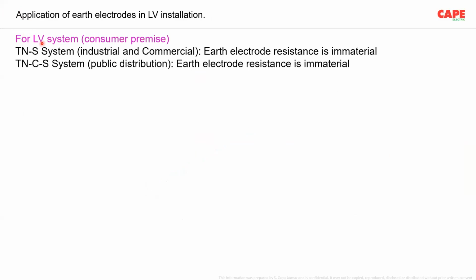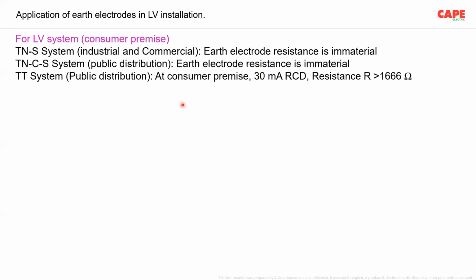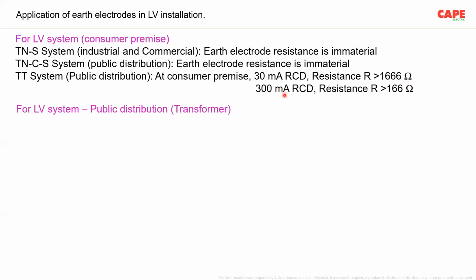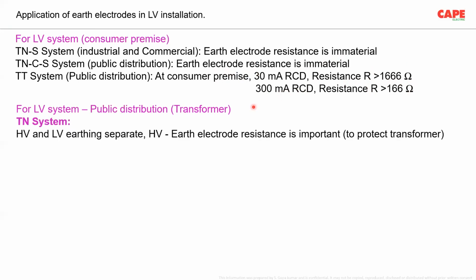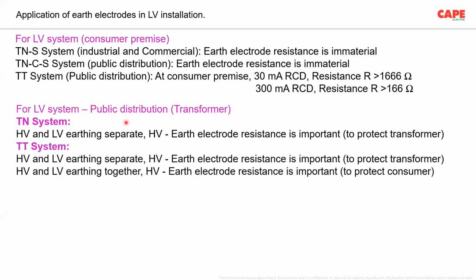Now, you know very well that for a low voltage consumer premise, if you go for a TN-S system, earth electrode resistance is immaterial. If you go for a TN-C-S system, earth electrode resistance is immaterial. If you go for a TT system, it can be anything, 1666 or 166 ohms, depending upon your RCD value. For public distribution, the power supply company can have the HT side of the earth electrode at a certain value in order to reduce the temporary overvoltage in the consumer premise if they go for a TT system.